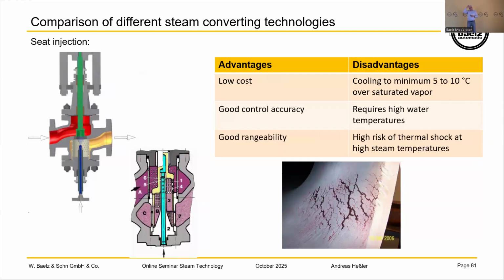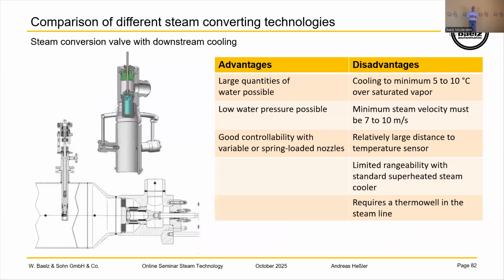And here I just want to show you real quick, what you can read later, the disadvantages and advantages of the different kinds of steam converting valves, in this case the ring and seat injection. The big disadvantage of the seat injection is that you may have a high risk of thermal shock inside the valve. Then we have the ring, meaning the pressure reduction and the cooling after the valve. Here the big advantage is to put the spraying outside of the valve, so we have no destruction inside the valve.